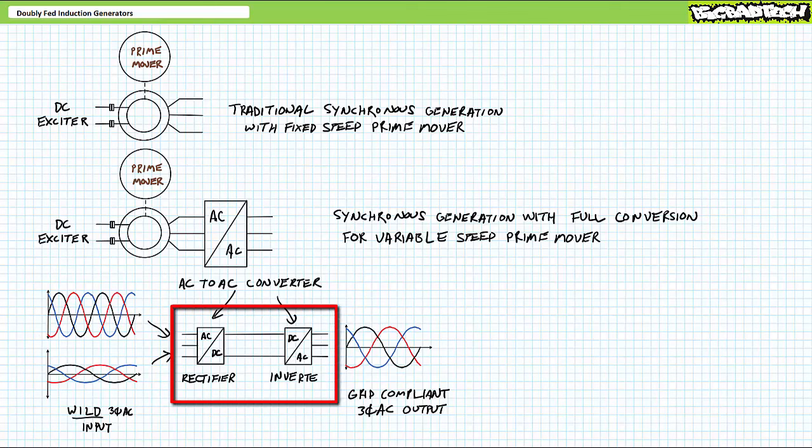A wind turbine generator making use of a simple induction-style generator could theoretically self-regulate rotational speed inside a given range by catching or spilling excess wind, by pitching or turning the blades into or out of the wind, thereby keeping generator output inside a desired specification. This does allow for a degree of speed variability, but not much.